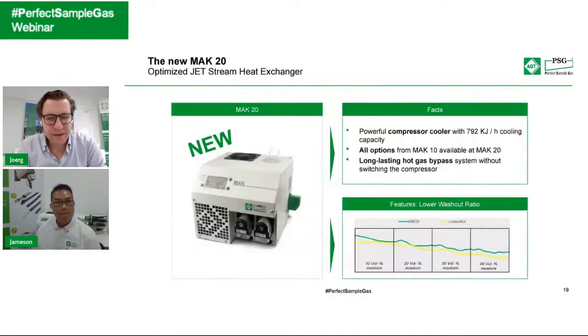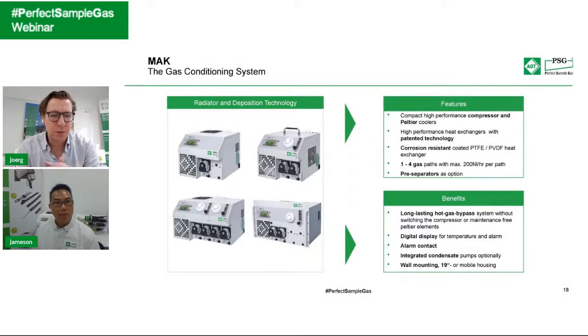So Jameson, for the setup or layout of the cooler, would you recommend to use 1 or 2 heat exchangers? I would strongly recommend 1 cooler with 2 exchangers. The reason is that people are investing in a cooler, which is the most expensive component in the sampling system. If we are investing in the cooler with 1 exchanger, and you add a small price adder to have a dual exchanger, that has a big impact on why a dual exchanger is better than 1. It really saves so much trouble in the whole configuration. So you would add this as an additional backup, so to say.